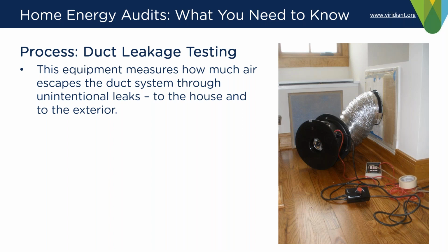Some leak very little. It's possible to get them essentially airtight, and some installers do. And then I find many houses where leakage is what I call catastrophic, where 20 or even 30% of the air moving through the system is not getting to where it's supposed to go. So you can imagine what that does to your costs for heating and cooling if 30% of the air is just going somewhere else.